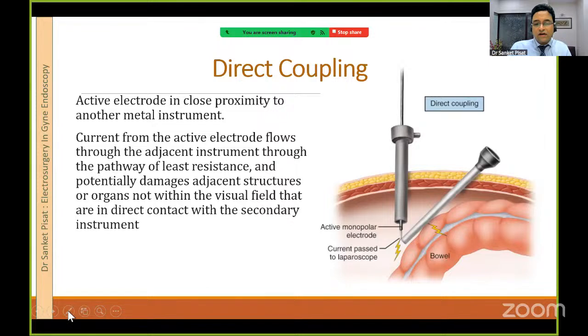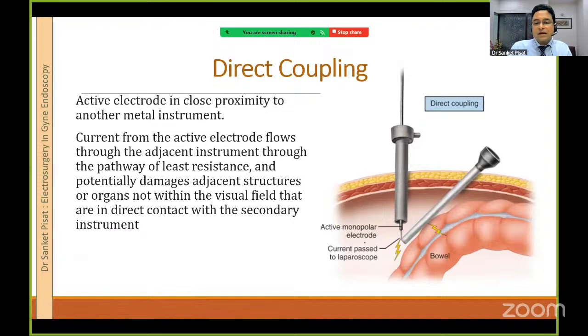Generally, the current should go from here, into the organ where you're operating, and then it should return to the return electrode, which is placed under the patient's body. However, we know that electricity and saline or water, fluid, by laws of physics, always seek the path of least resistance. Because there is another metallic object right here in close proximity, the current jumps from this object to this object and then goes back into the patient electrode. This results because you have created a pathway of lesser resistance, and it potentially damages adjacent structures.